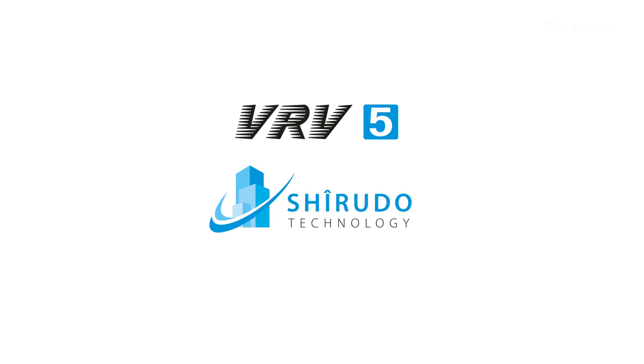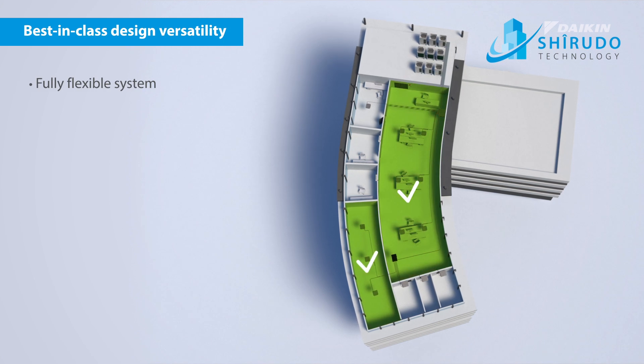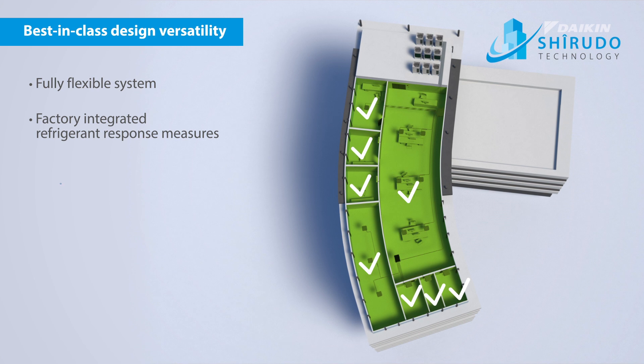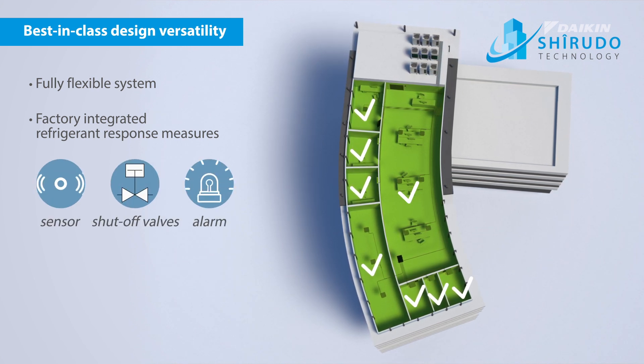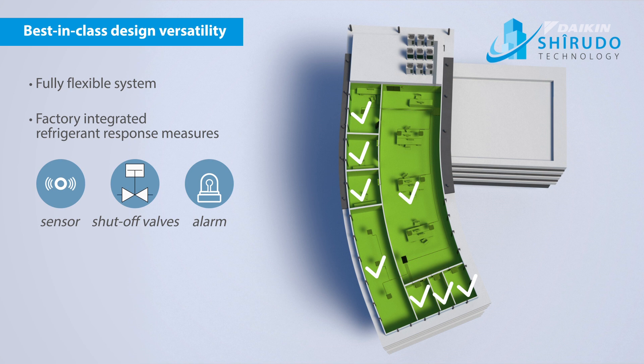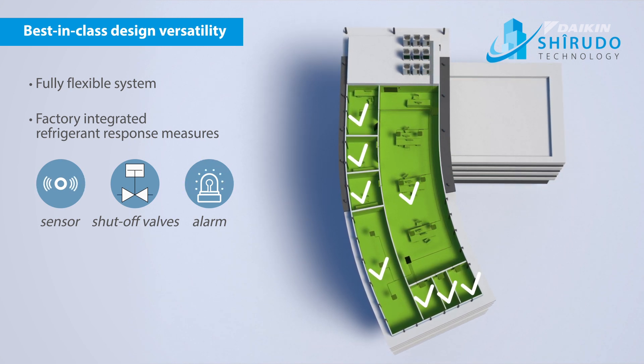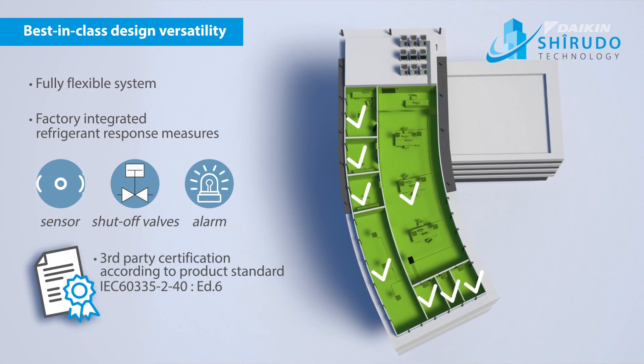Unless you choose the VRV5 with Shirudo Technology. With Shirudo Technology you have a very versatile system to accurately control the indoor climate. Thanks to the factory integrated refrigerant response measures, Daikin guarantees peace of mind for compliance to the specific product standard of IEC 60335-2-40 Edition 6 out of the box. And it's also third party approved by a notified body.